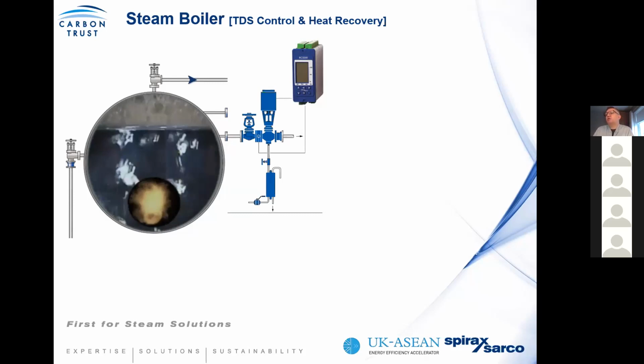Now, boiler manufacturers would recommend certain upper TDS control limits. And for a standard boiler, they would recommend, say, 5,000 microsiemens. So in other words, you should control to an upper conductivity of 5,000 microsiemens. However, you should consult with your water specialist, because alkalinity or silica or other water properties will determine what your cycles of concentration should be. So in other words, which comes first, the boiler manufacturer's recommendation or the analysis of your feed water from your water specialist? You could find that although your boiler is designed to operate to 3,000 or 5,000 microsiemens, you may have to reduce the conductivity to control silica, for example, or alkalinity.